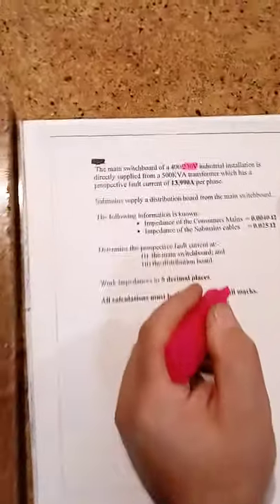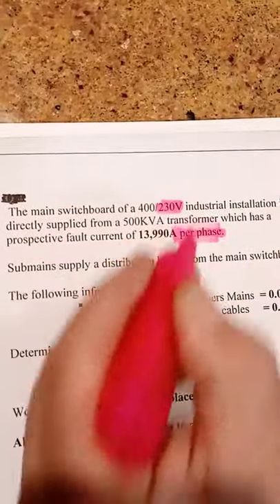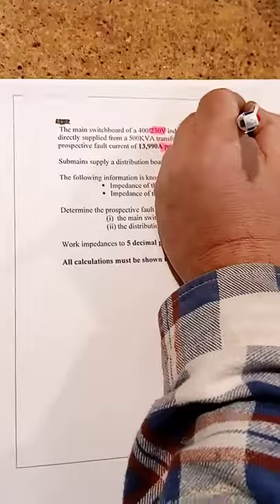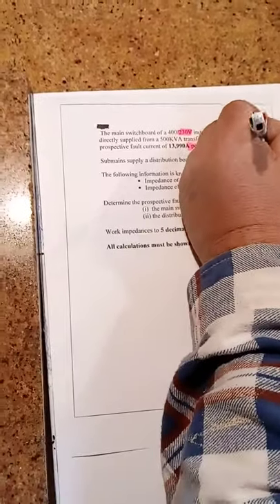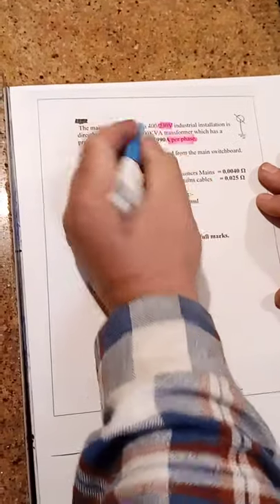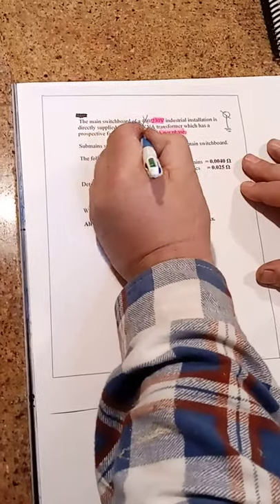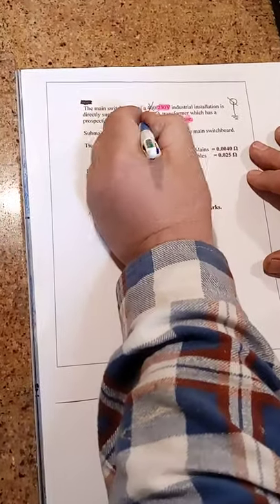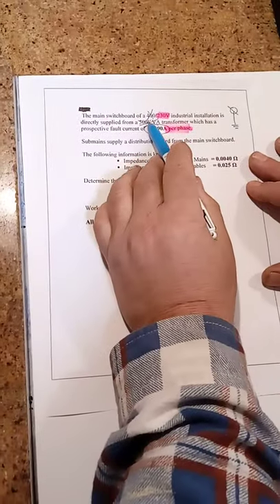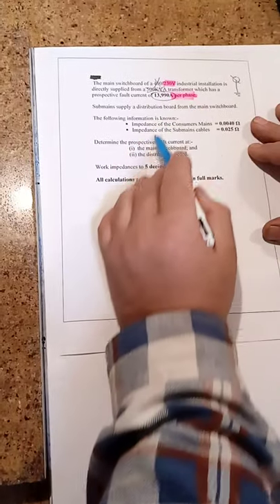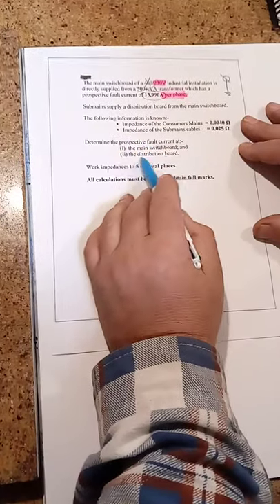For example, 230 volt - that applies because we have this thing down here called per phase. Now when we talk about per phase, a phase talks about down to earth. And that's where we're getting these fault currents from here down to earth. So we don't need the 400 volts and it says we have a prospective fault current of 13,990 amps. We just want to know the short circuit current down to earth at the main switchboard and at the distribution board.